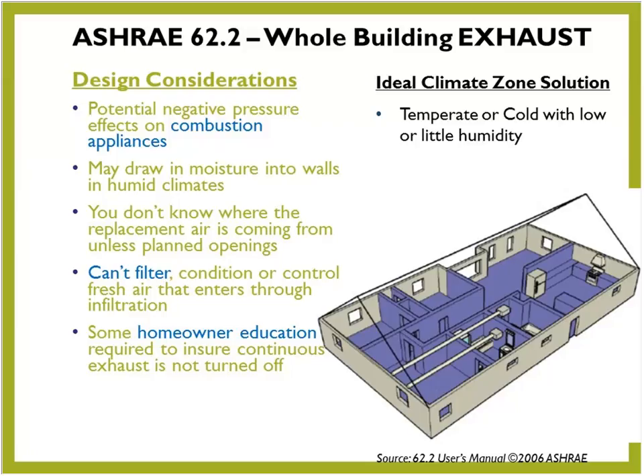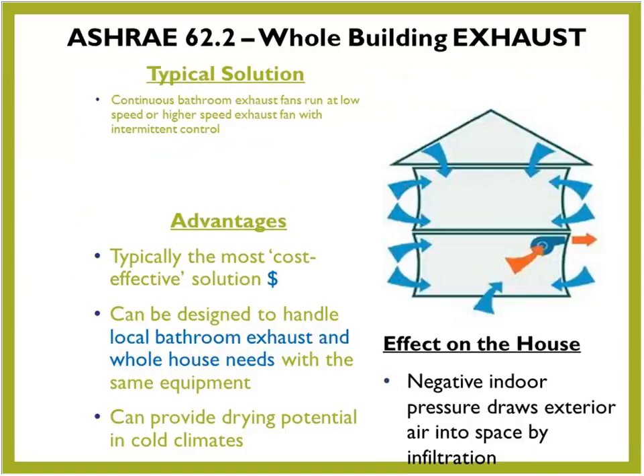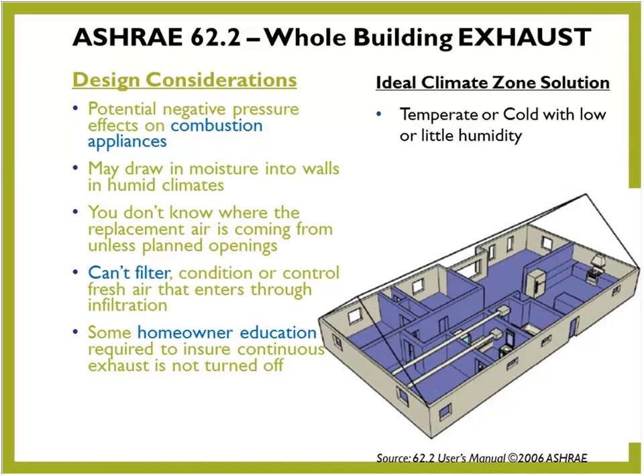For our climate, however, using exhaust-only ventilation is more appropriate than, say, supply ventilation, because we're relying, again, on air leaking through that building shell. So in the winter, when you've got a big difference in temperature from outside to inside, using cold, dry air as your makeup air, if you will, or your fresh air supply, can actually have a drying effect on the building components. So that's a benefit of exhaust only as well for our climate.